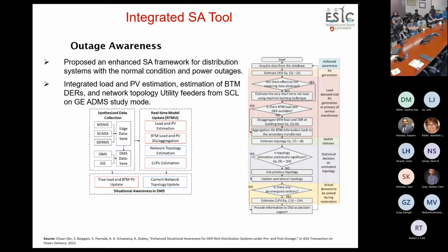Then there's the network side, because you always have to consider design topology versus operational topology - they're completely different. Even when a crew says they turned on a breaker or a tie line, that's not actually reflected in the control center because it's manually operated, and the operator doesn't know the exact topology right now. People get supply, but mapping issues still exist.